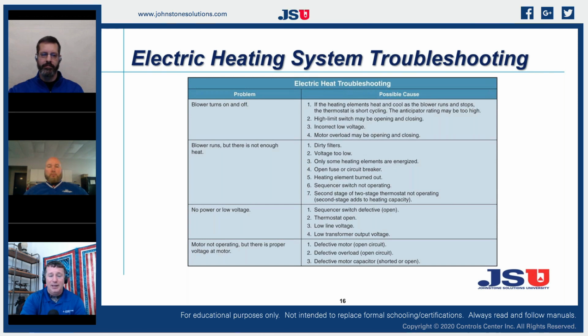And just a handy little troubleshoot on electric furnaces. So blower turns on and off, then we've got some kind of cycling. Well, then we need to get in and take a look at our limits. We need to verify our motor overload, because so many of our new ECM motors will shut themselves down. So an ECM motor, typically in that 0.8 to 0.9 inches of static, is going to protect itself and reduce. If it's a true variable speed ECM, if it hits that temperature limit in its module on the back of the motor, it will reduce itself down to 35% and it will stay there.